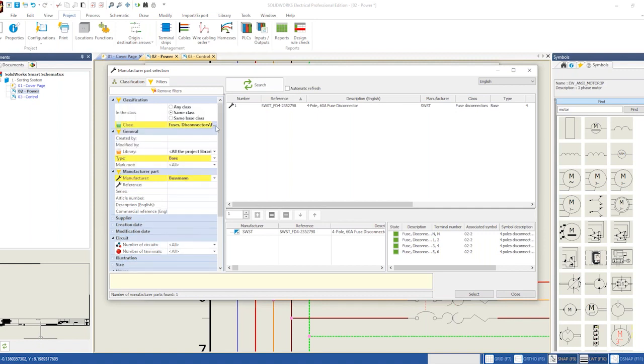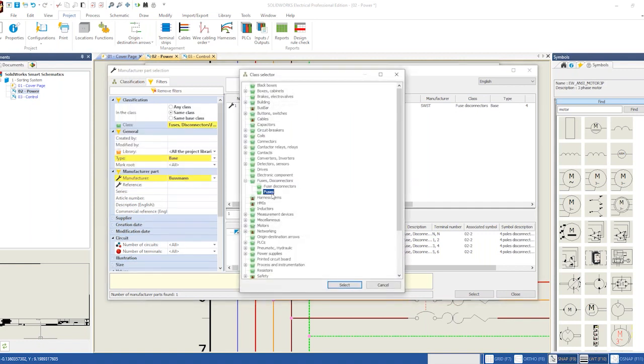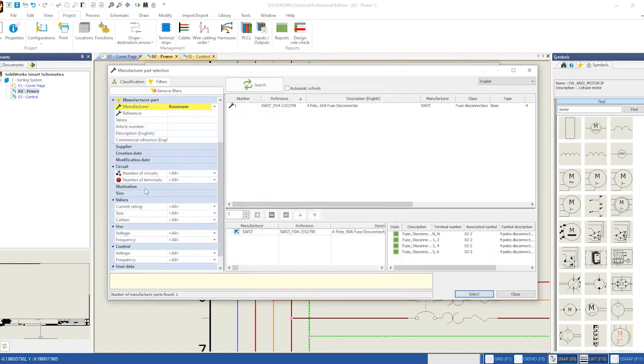So I'm not looking for a fuse disconnector, I need to look for an actual fuse, so we'll select fuses, come down for my current rating again, and give me everything that's a 20 amp fuse by Bussmann - and I only technically have one in my library. In this particular case I need 4 of them, so I need 4 of those to build up that complete part.